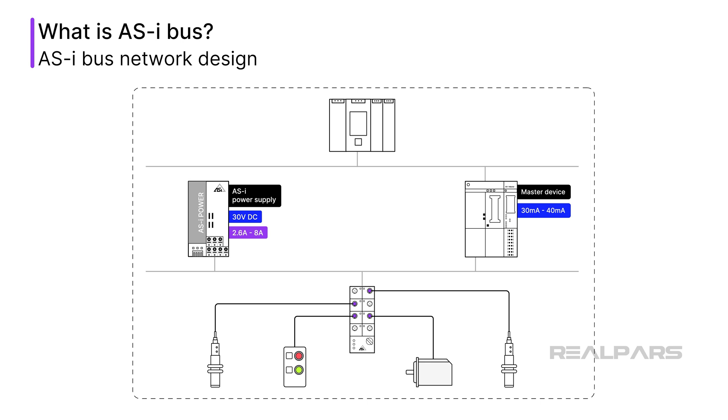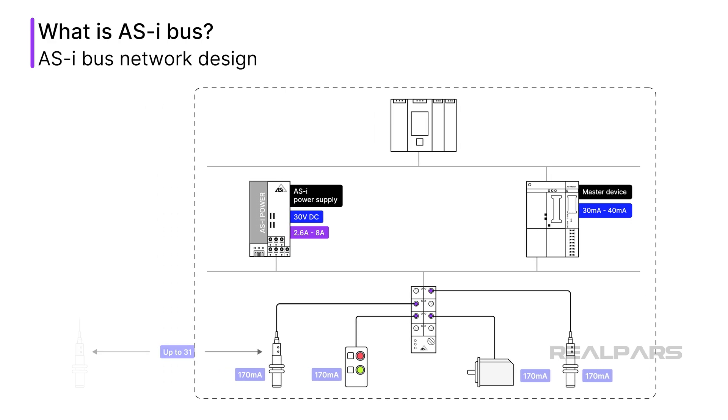Slave devices are limited to 170 milliamps to ensure reliability. A standard AS-i bus segment can support up to 31 slave devices.